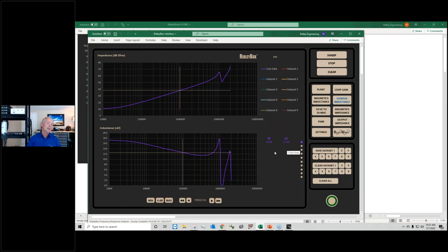So this is not something you'll see in a data sheet from a manufacturer, that the leakage inductance of a transformer is moving with frequency. This is really important to you as a circuit designer, because which value of leakage do you use? If you're designing a snubber that's going to be ringing at 10 megahertz, you need to know this lowest value here. We have to discount these parts because there's a resonance going on, so 11 microhenries is what you'd use to design your snubber. Maybe the value at 100 kilohertz is what you'd use to estimate your dissipation, and maybe you'd use that one inside LTSPICE. I don't know, but the leakage changes with frequency.